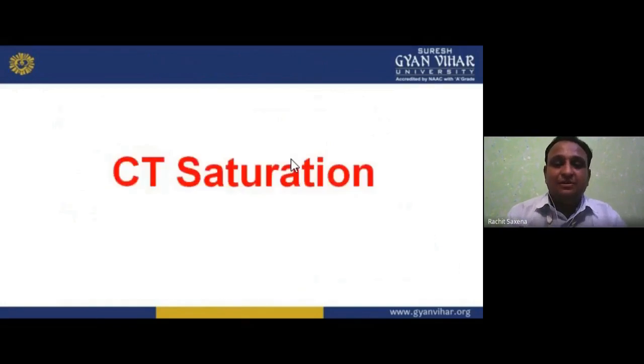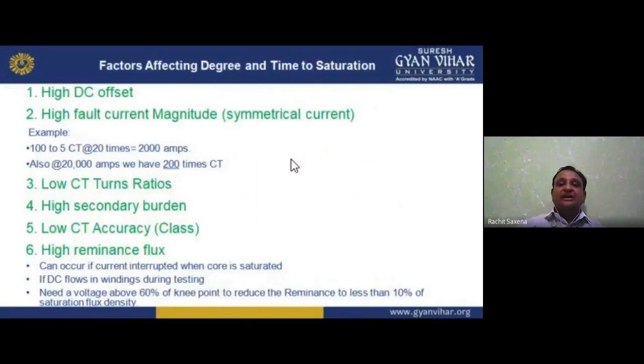I hope you understand. Now, CT saturation. The factors affecting the degree and time to saturation are high DC offset, high fault current magnitude, and symmetrical current. For example, a 100 to 5 CT at 20 times means 2000 amperes, and at 20,000 amperes we have 200 times the CT rating. Other factors are low CT turn ratio, high secondary burden, and low CT accuracy class. High remanence flux can occur if current is interrupted when the core is saturated. If DC flows in a winding during testing, we need a voltage above 60% of the knee point to reduce the remanence to less than 10% of the saturation flux density. So these are the factors affecting the degree and time to saturation. I hope you understand.